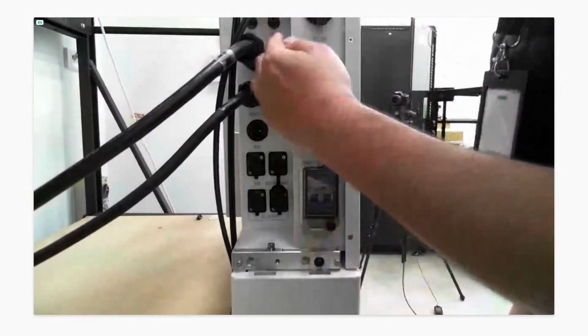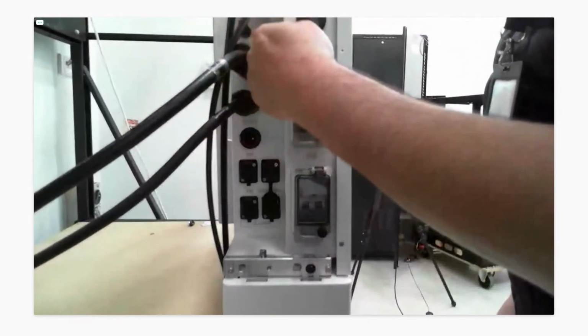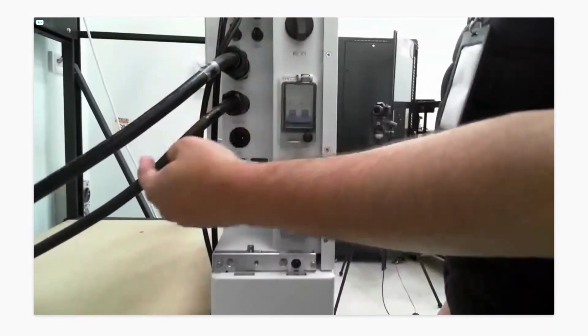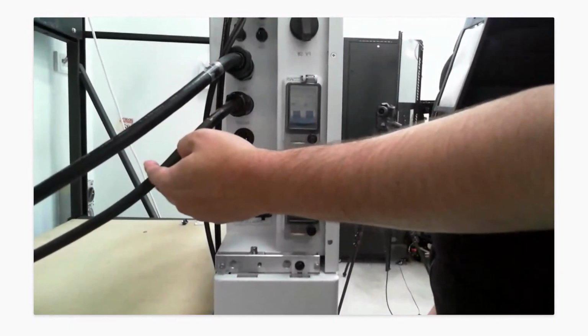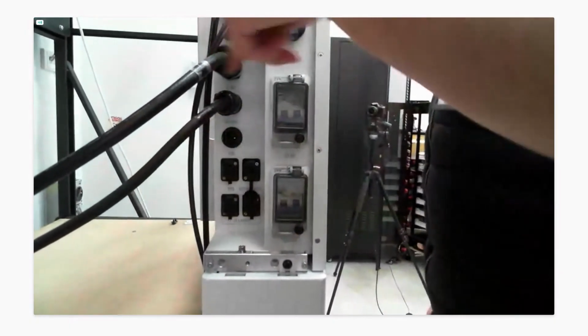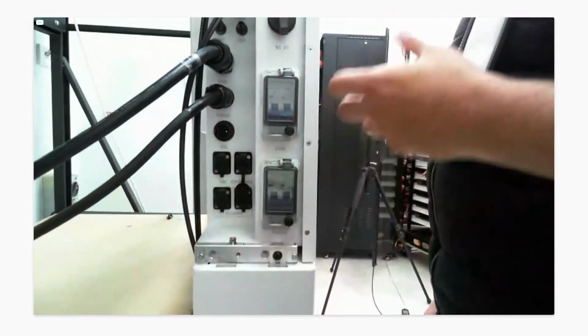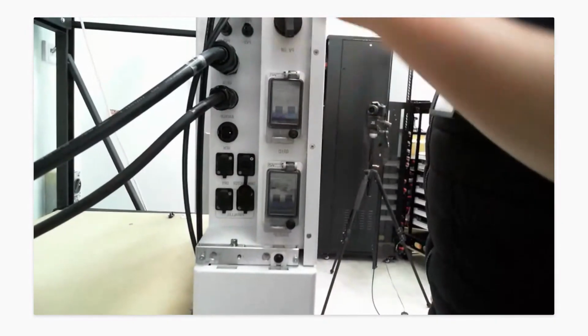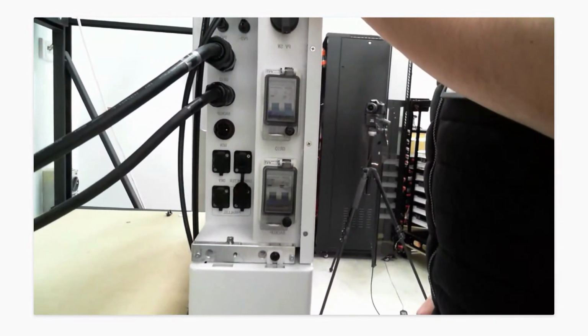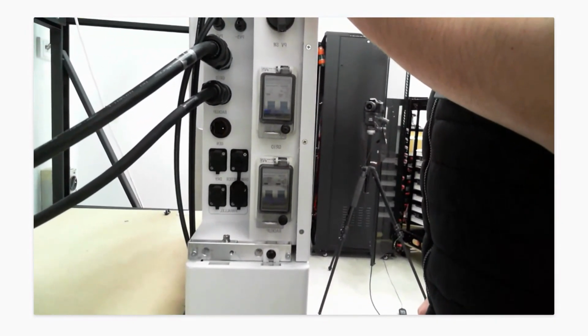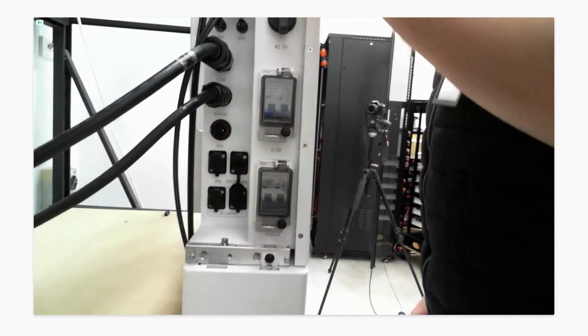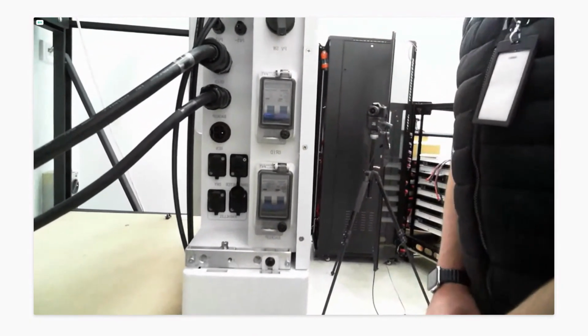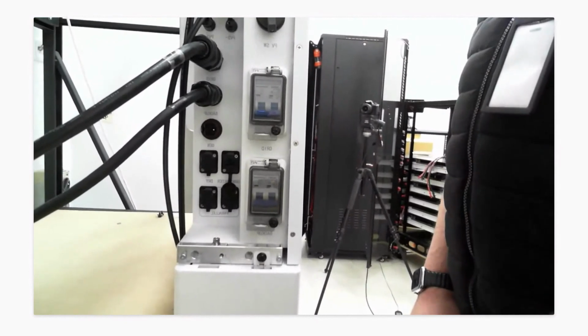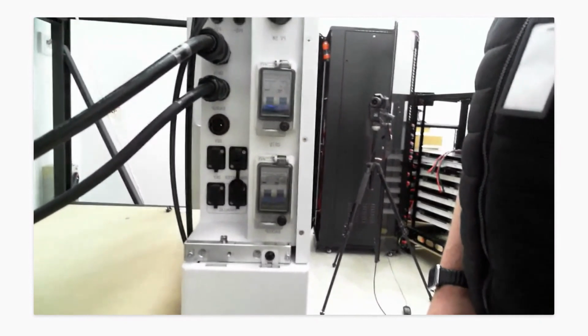The pass through can pass from the grid input through to the EPS output. This is 40 amps from the grid. That's pretty good. So up to 40 amps can come in from the grid through our inverter system and out on the backup circuit. But when you are in your microgrid mode or backup mode, the inverter is only rated to provide 30 amps of backup for the 7 kilowatt inverter. So when the grid's down, you're only going to get 30 amps. Correct. What does that work out to in kilowatts? 7. Okay, well that sounds pretty reasonable.